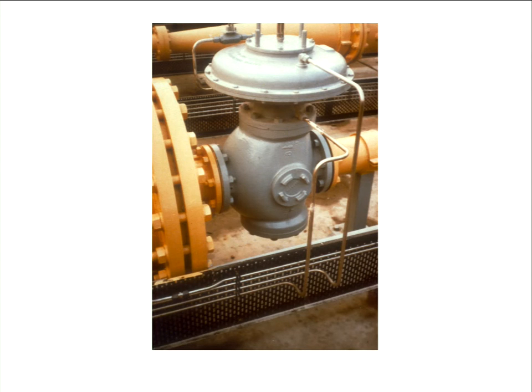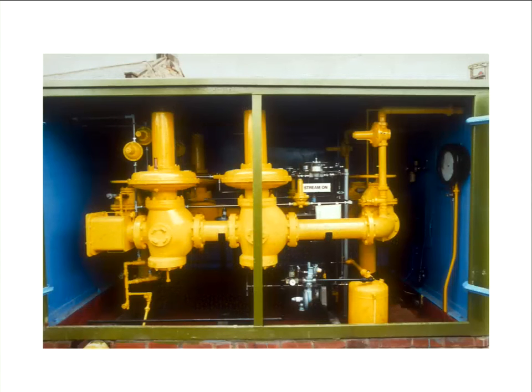typically you've got your different pipeline pressure designed to a pressure regime. So let's say I've got my national system here at 70 bar, and I've got my control installation there, and this is, say, 38 bar. So this one might be managed from a central control room. The sort of job I did for a number of years was looking at the gas demand, forecasting it, and then monitoring what had actually occurred, and then we might adjust the flow on here, say from 5 million a day to 6 million a day, and looking at how that pressure was varying.